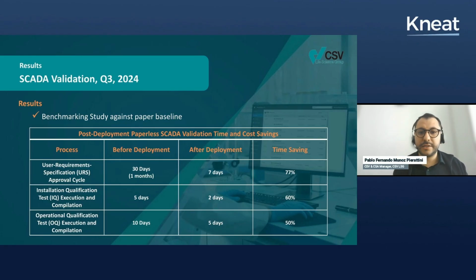And after deployment, 7 days. So we have a very big time saving in this case, approximately 80%. Otherwise, for the installation qualification and for the operational qualification, in terms of execution and compilation, we save most time during the compilation, obviously. So before the deployment, we use 5 days to perform the installation qualification testing and 10 days to perform the operational qualification testing. So after the deployment, the time is reduced more or less 50%.